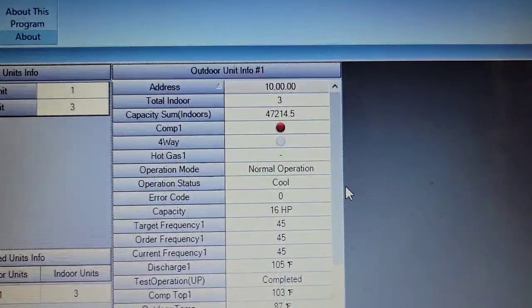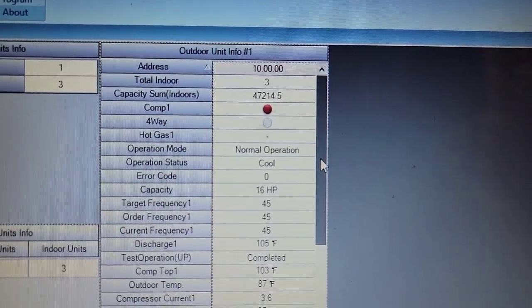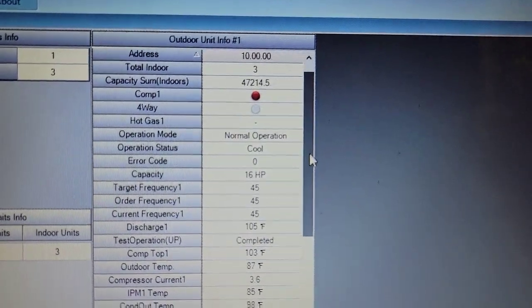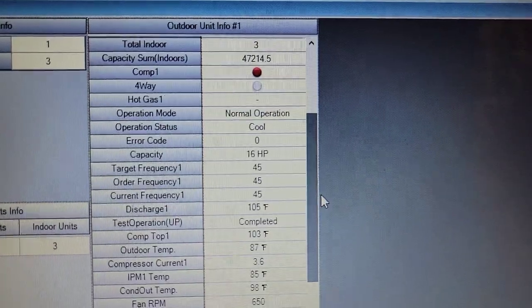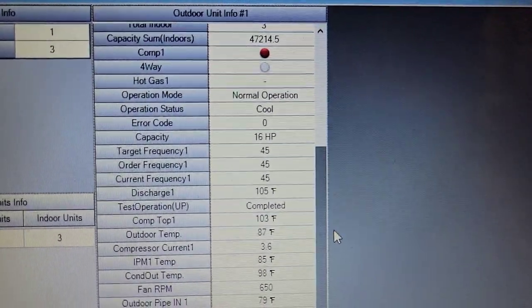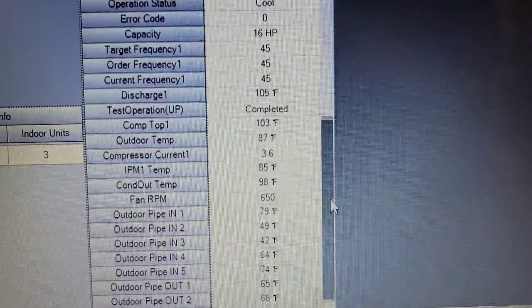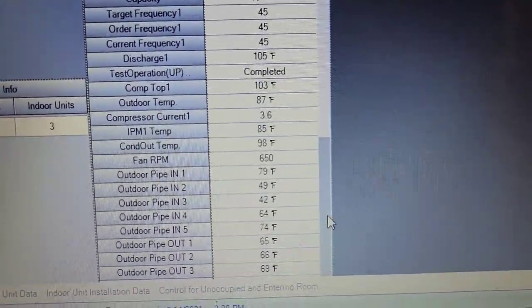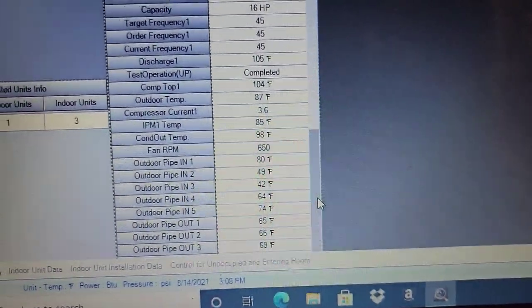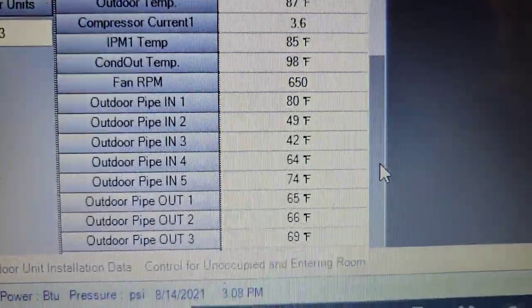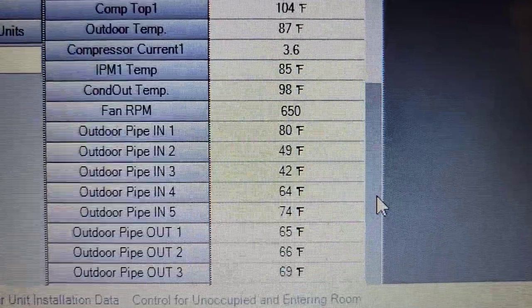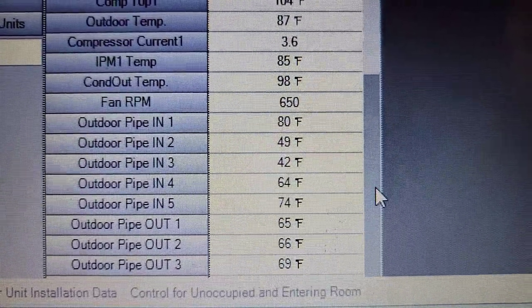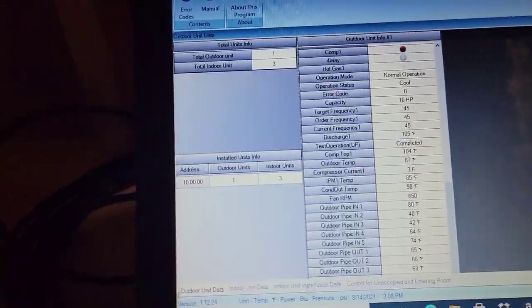This is our outdoor unit. Total indoor units is three. Capacity for the sum of those indoor units is 47,214. We've got compressor is on. We've got no error codes. Operation is cooling. Discharge temperature is 105. Compressor top temperature is 103. Fan RPM for the outdoor motor is 650. I'm using pipe number two, three, and four for this unit, and we've got 49 degrees, 42 degrees, and 64 degrees.